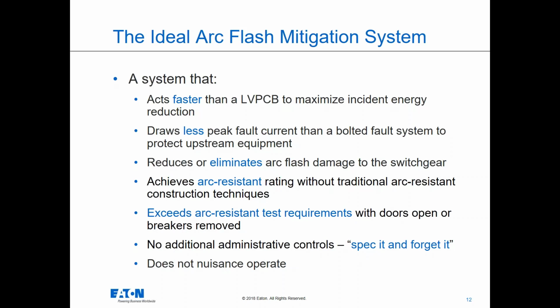to get replaced, or usually months. It would be great to achieve arc flash ratings, get that ANSI C37.20.7 rating, without the traditional arc-resistant construction techniques and without the limitations about doors. It would be nice to be able to IR scan a piece of gear without having to wear all the heavy PPE. It would also be nice to not nuisance operate, and to not have to worry about desensitizing any of my equipment, to just navigate around the traditional methods, the traditional systems that are in the gear and going to be present anyway.